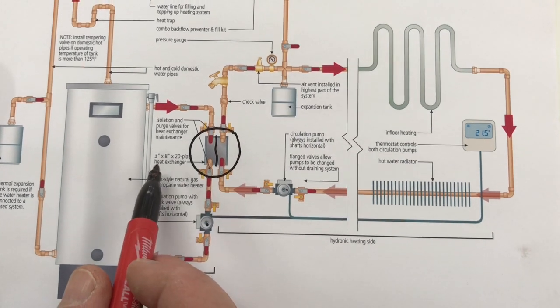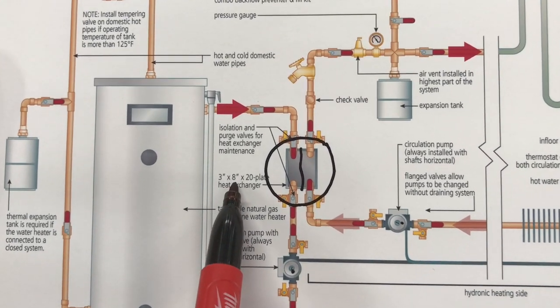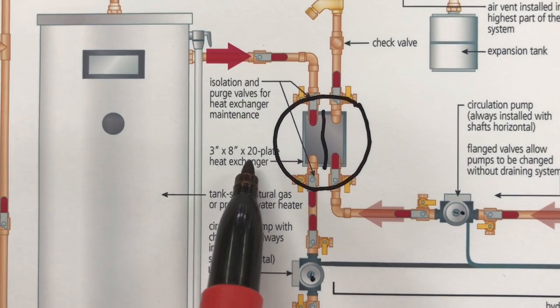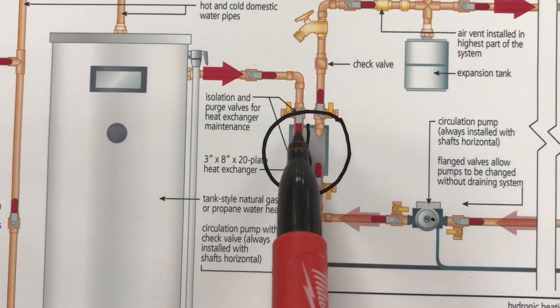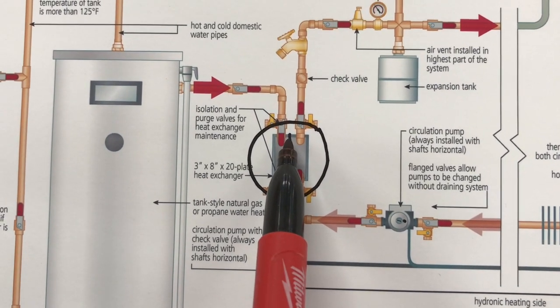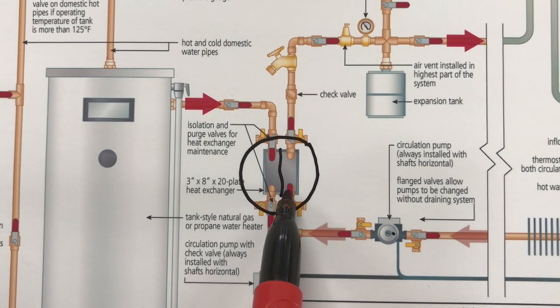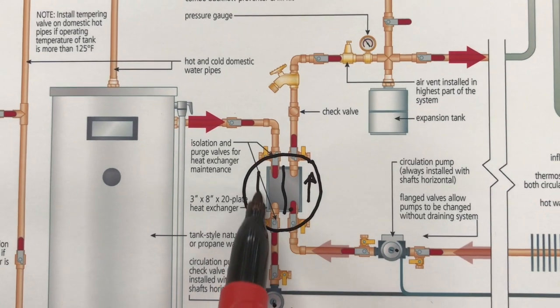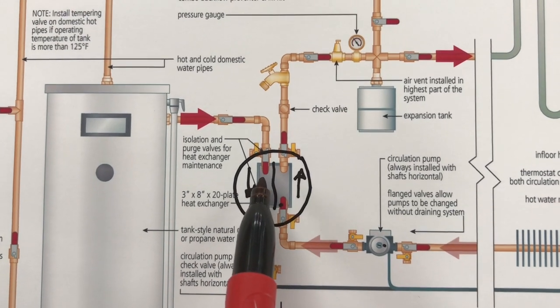Now a typical heat exchanger like this, a flat plate style, works really well. Three by eight inches with about 20 plates I find sufficient for most houses where I live in the fairly cold part of Canada. The hot water from the tank heats this side of the exchanger and the water from the heating system picks up that heat from the other side. You'll notice that the flow of water runs opposite to the flow through the other side of the exchanger. That's the way you get the most heat exchange.